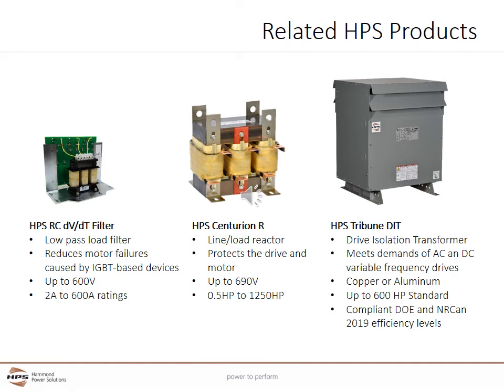Hammond Power Solutions has several complementary products for power quality problems associated with variable frequency drives. The HPS RC DVDT filter is designed to reduce motor failures caused by reflective waves from the pulse-width-modulated output of VFDs with long lead lengths of up to 1000 feet between the motor and the drive. The HPS Centurion R Reactor mitigates current harmonics and protects the VFD from voltage spikes, and can also be used on the load side of the VFD with lead lengths up to 500 feet. The HPS Tribune drive isolation transformer is designed for both AC and DC variable speed drives and can provide any required voltage change. HPS offers two lines: the Tribune E, a high-efficiency design compliant with Canadian NRCan 2019 efficiency requirements, and the Base Tribune, which meets U.S. DOE energy efficiency exemptions.